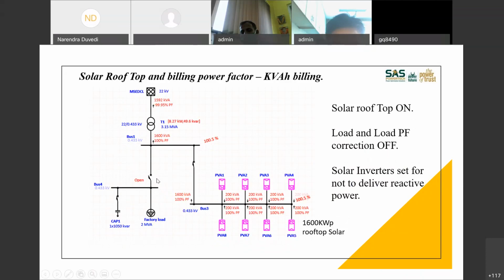What I have done here is I have disconnected the load totally, and typically in your case it is a holiday. I mean, the plant is not working and the solar system is still working. Here the entire power which is generated is now pumped back to the grid. Even if you have a net meter, or even if you don't have a net meter, net metering is a commercial arrangement. Whatever you pump back, whether it should be charged or not, is a commercial arrangement. But whenever you connect it to the grid through a transformer, power is bound to go back to the grid unless you stop it going there.